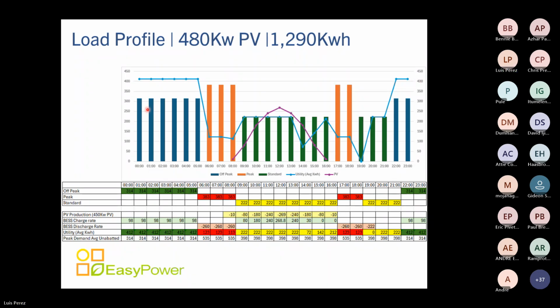Now those bars on the bar chart are averages, not the peak. And that is not what the meter uses to give you your peak demand. What the meter uses to give you your peak demand is the actual peak, which we've seen in this study is close to 530 kilowatts during peak time. So during this time, we can see peaks of over 535 kVA.